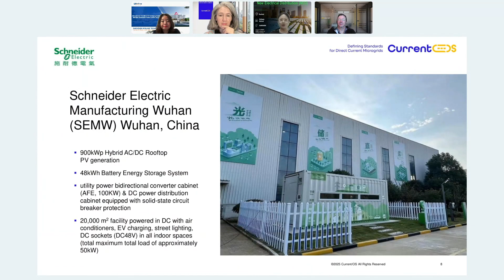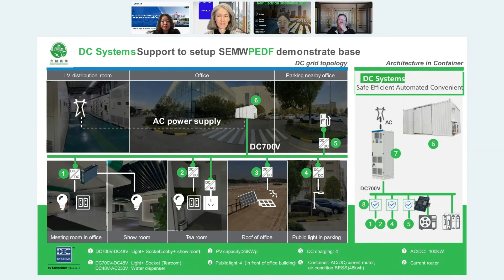Let's do a brief review of the DC topology. It's a grid-connected system, so the AC power supply is connected to the container and then to the interlink converter, changing from AC to DC. The bus running as the backbone is DC 700 volt. The sources and loads are connected to the DC backbone. As you can see, lighting, USB-C sockets, and street lights are powered through DC-DC conversion. The PV bus and EV chargers are also connected to the DC bus. For some AC essential loads, we use DC to AC conversion to power them as well.